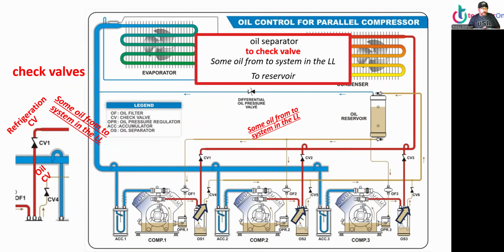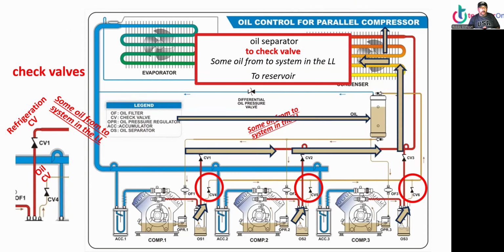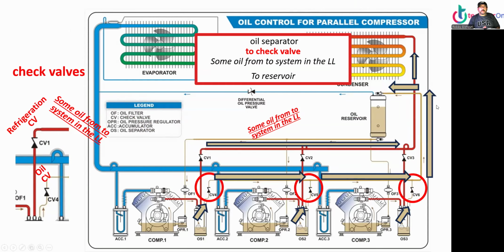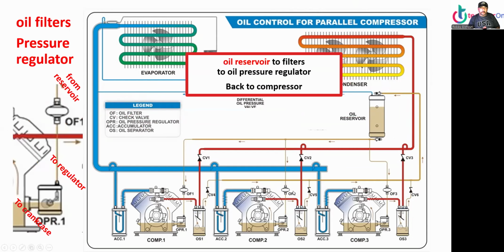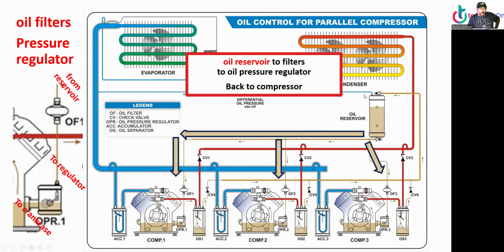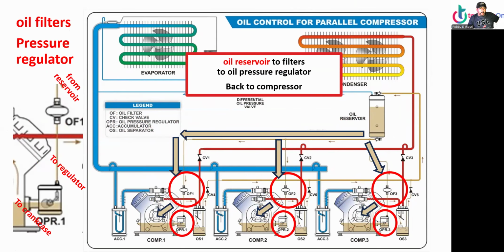And then it goes out to the oil check valve, and some of the oil goes to the liquid line. Okay, and then it goes to the check valve. Now, some of the oil, a small amount, goes to the liquid line, and most of the oil goes to the oil reservoir. Now, from the oil reservoir it goes back to the filter, and back to the oil pressure regulator, back to the compressor.